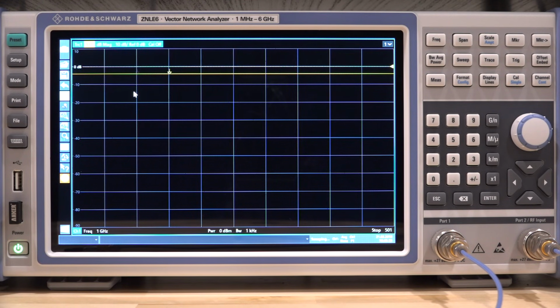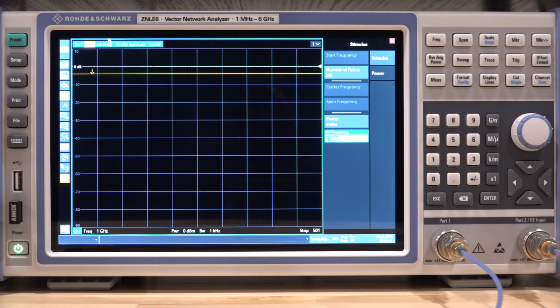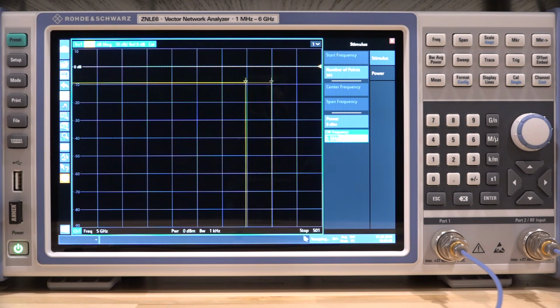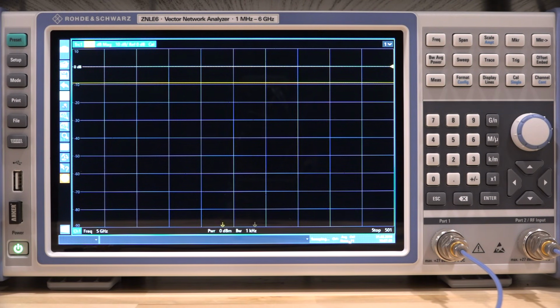Now, another thing I noticed, which is a little bit annoying, is that as you can see right now, when the frequency is at 1 gigahertz with a bandwidth of 1 kilohertz, we are on channel 1, port 1 only, because I'm measuring S11, so port 1 should be the only port that has incident power. But if I go ahead and change the frequency, so let's click on frequency here, and I'm going to change the frequency from 1 gigahertz, let's say, to 5 gigahertz. I'm changing nothing else, and then all of a sudden it starts doing port 1 and port 2. I'm not sure why it does that. I think it's a bug in the firmware, and hopefully this can be fixed.